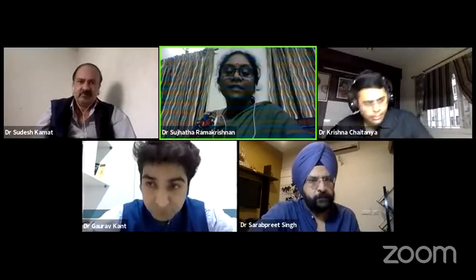How frequently? Krishna, can I answer this? Yes, ma'am. So I'll just tell you our practice. Temperature is checked almost every day. If it's a box type of incubator, we have a calibrated thermometer inside the incubator. And similarly, we use a thermocouple, which goes on a full circle in the entire week. One day we check the benchtop incubator, and we don't check in just one place. It's a kind of temperature mapping. We put it in one corner, and it's specified that each day it is different. Similarly, we also check the laminar airflow temperature. We also check the ICSI system temperature.